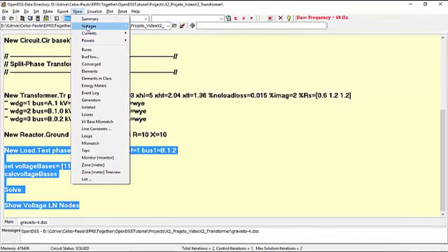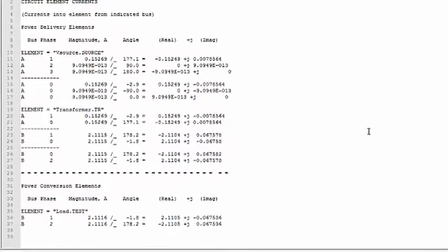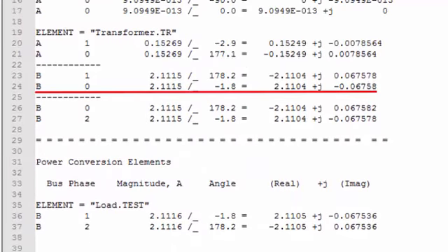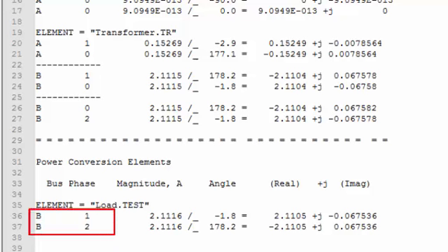Finally, observing the currents in elements report, one might be induced to think that the load current flows through ground. However, this is not the case. Both the secondary and the tertiary windings are connected to ground, but they are also connected to each other. Then, the same current flows through both windings, not through ground. The apparent misunderstanding is due to the fact that the currents flowing in each winding are reported separately from each other. In fact, there is no load connected to ground in this example.